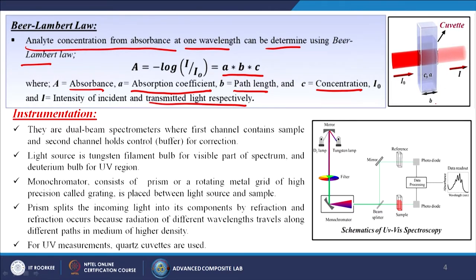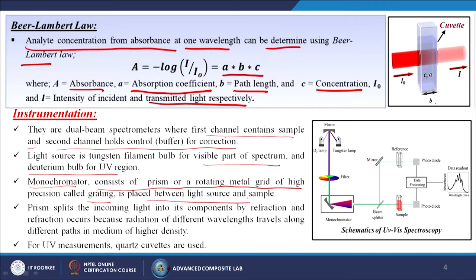So how are we going to measure this? Generally they are dual beam spectrometers where the first channel contains the sample and the second channel holds the control for corrections, generally for the buffer. The light source is a tungsten filament bulb for the visible part of the spectrum and a deuterium bulb for the UV region. A monochromator consisting of a prism or a rotating metal grid of high precision called a grating is placed between the light source and the sample. We have the D2 lamp and the tungsten lamp, a mirror, a filter, a monochromator, then a beam splitter, then a mirror, falling through the reference and then a photodiode and data processing. From here another beam goes directly to the sample, through another photodiode, then data processing, and we get the results.